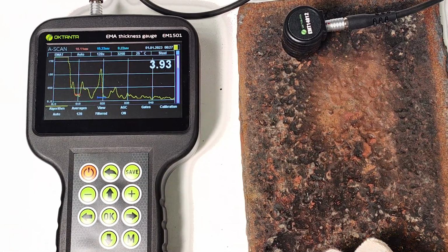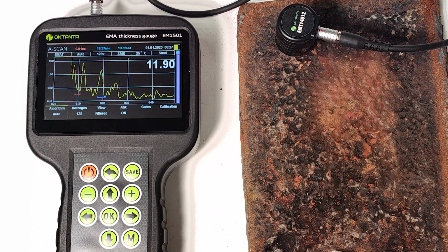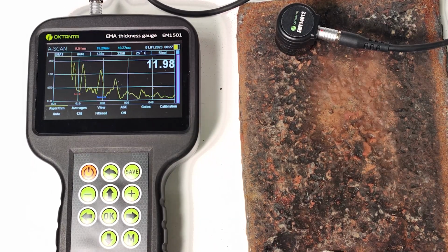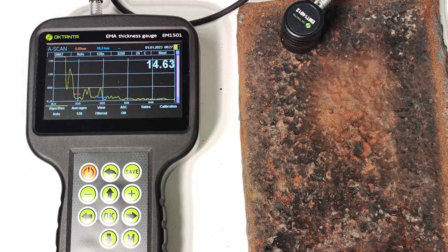When measuring the thickness of heavily contaminated or rusted objects, objects made by casting, or objects with special external or internal geometric or material characteristics, the use of A-scan may be required to obtain reliable measurements.